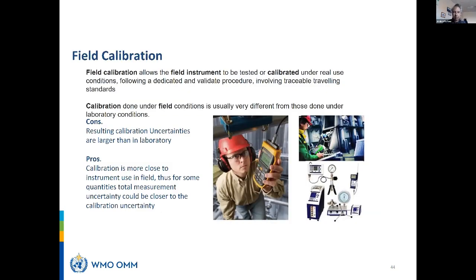We can do field calibration, both in industry and in the environment. They are very useful when you cannot remove the instruments, and because you're in the same condition in which the instrument works. So, for example, the data logger is at minus 10 degrees, and you are sure that if it gives you this answer, it is the answer at minus 10. It's better than just sending it to a lab.